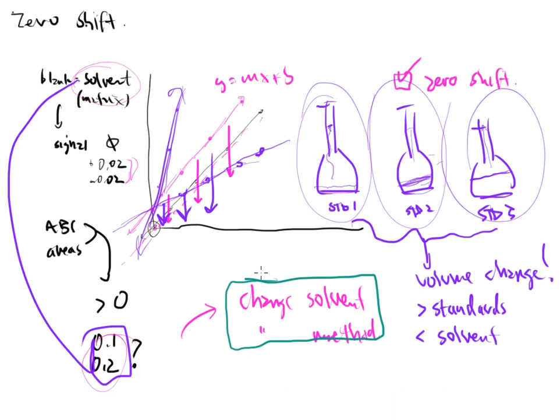And our HPLCs have it as well. But never check it. Make sure the box is blank every time that you make a calibration standard set and run them. And I think that you'll get some good data because of it. Say no to zero shift. Let that be a take-home message. And now you know why.